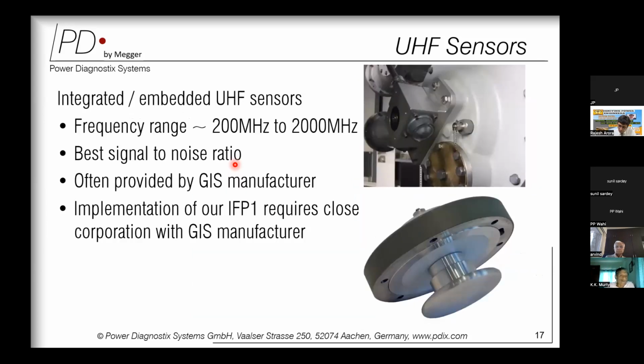Now coming to today's generation of GIS, which is already loaded with an integrated or embedded UHF sensor, something like this, spanning a frequency range from 100 or 200 megahertz to 2000 megahertz, which provides a broadband measurement response. Since these are integrated into the GIS, what we see on the screen is an antenna embedded into the GIS, and the outer connection is only the N-type UHF connection, which is used for doing the measurement or capturing the signal.